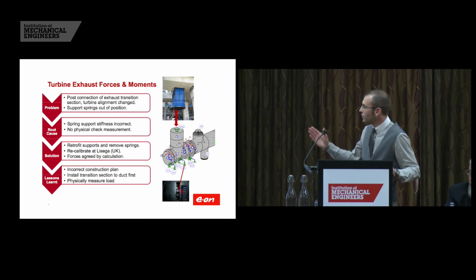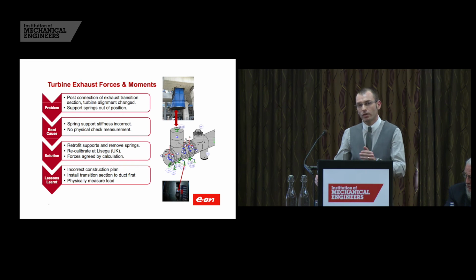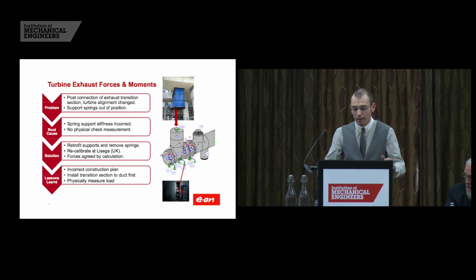In future, if we install the exhaust transition section onto the air-cooled condenser duct first and place it in position, then we can set up a rig and do a physical measurement of the loads by pulleys and load cells, therefore proving the loads are within the limits of the steam turbine manufacturer.